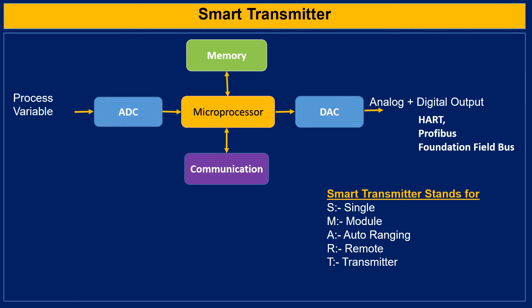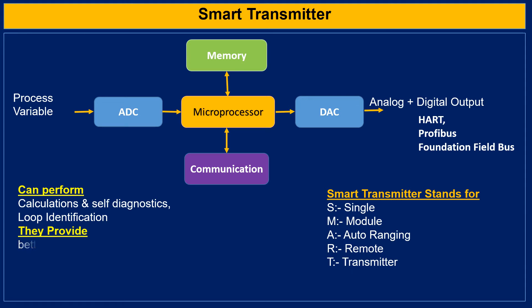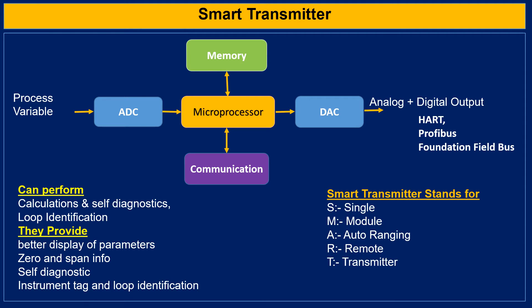Smart transmitters utilize a microprocessor and memory as their internal units. These transmitters can perform calculations and self-diagnostics. They provide a better display of parameters, zero and span information, self-diagnostic instrumentation tag or instrumentation loop identification. They have the additional capability of digital communication along with 4 to 20 mA signals over a two-wire loop system.